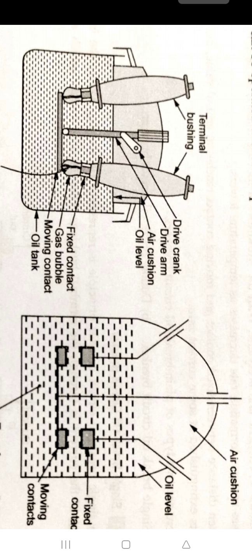When the contacts are separated, two arcs are drawn. Thus, there are two breaks in series. This can achieve rapid arc lengthening, which eliminates the need for a specially fast moving contact speed. But this introduces unequal voltage distribution across the breaks with uneven sharing of total interrupting duty. One break may take 70 to 80% of the interrupting duty.